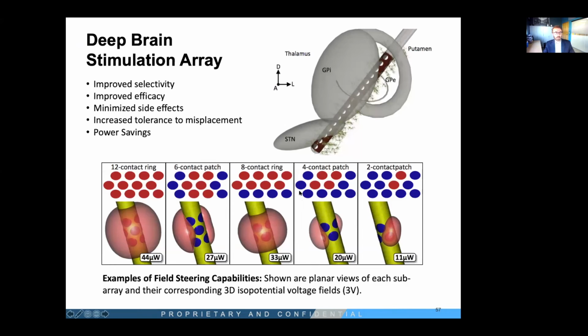And then moving a little bit into deep brain stimulation, this is some of the work that we did where we took a polymer array and wrapped it around a flexible carrier, really with the goal of providing more directionality in the stimulation. This is some modeling work that shows the different electric fields that can be generated as you activate different subsets of electrodes. The red electrodes are the activated electrodes, and the blue electrodes would be either neutral or return electrodes.